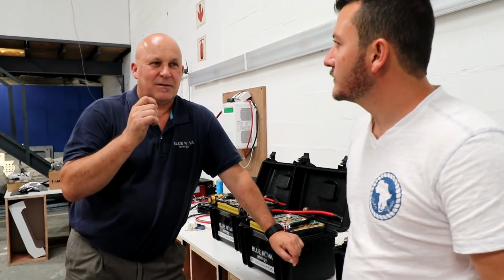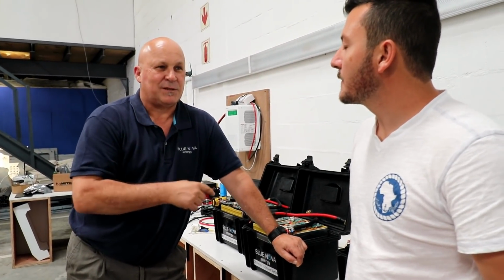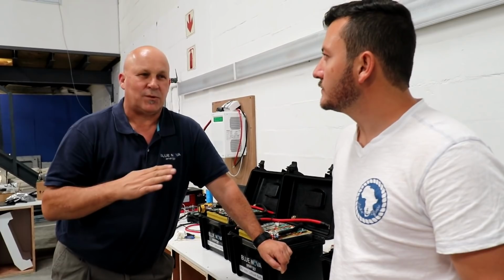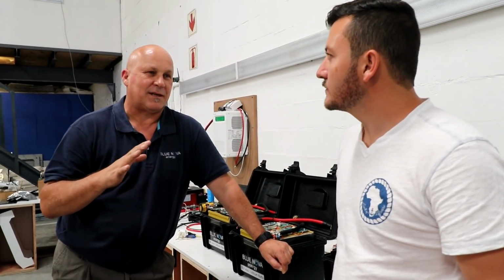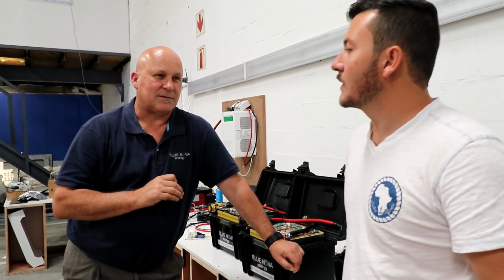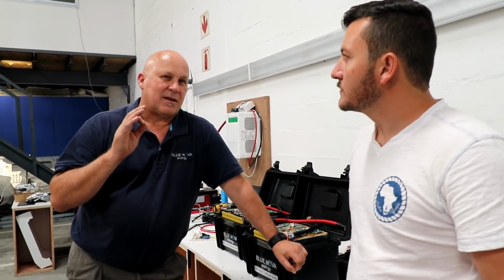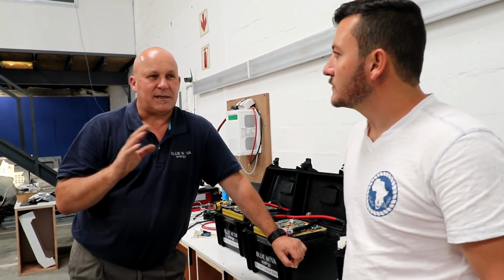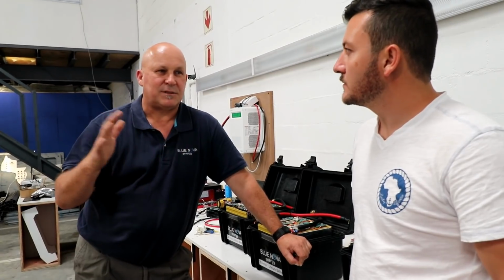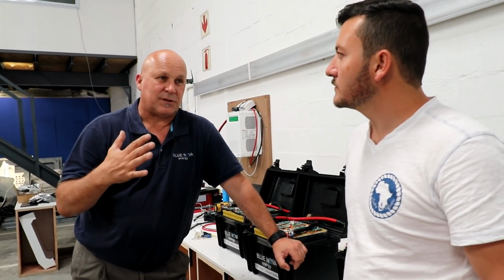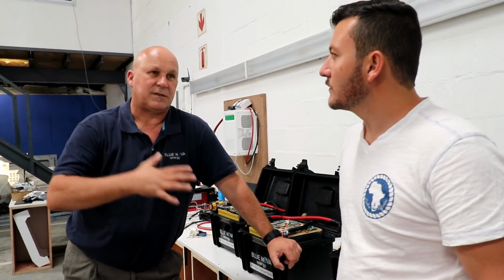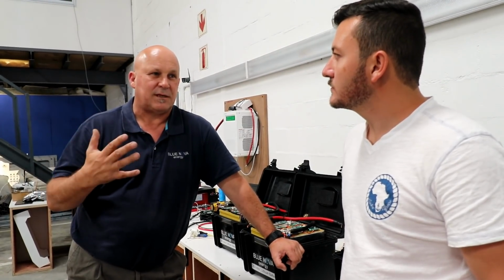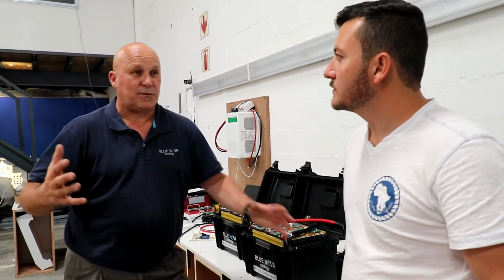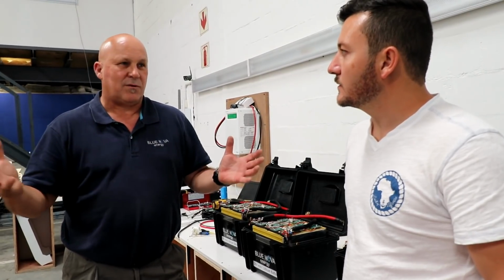The single most impressive thing about these batteries isn't the weight, size, or safety - it's the charge efficiency. These batteries have a charge efficiency of about 98%, sometimes 99% if you charge them slowly. A lead acid battery, when charged from 50% to 100% full, will lose up to 40% of the inbound energy, so you need 40% more solar power or generator capacity.